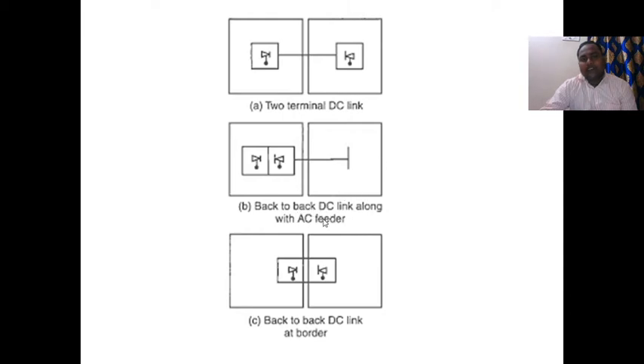Next one is a back-to-back DC link along with an AC feeder. This is an AC feeder. This is a back-to-back connection. The main application of a back-to-back link connection is to overcome the stability problem. If using only an AC feeder, there is a stability problem. If using a back-to-back connection, there is no matching of frequencies required. This is well suited in HVDC, back-to-back DC link along with AC feeder. Next, back-to-back DC link at the border. At the border, at the end points of systems, we use the DC link. So then there is no problem of stability. Synchronization is required when we use a back-to-back DC link within border lines. At the border means at the end of stations, we use the DC links.